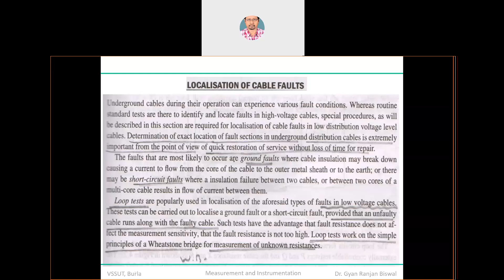We are supposed to discuss this under the Murray loop test and the Varley loop test. We will see both methods one by one. The essence of these measurements, when you talk about localization of the cable fault or identifying the exact location of the fault in underground cables, is that the fundamental principle of these tests is based on the Wheatstone bridge measurement. The Wheatstone bridge you use for the measurement of resistance, so the same scheme we are going to use. Let us discuss first the Murray loop test.